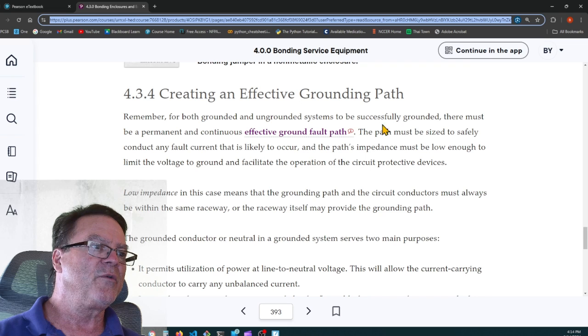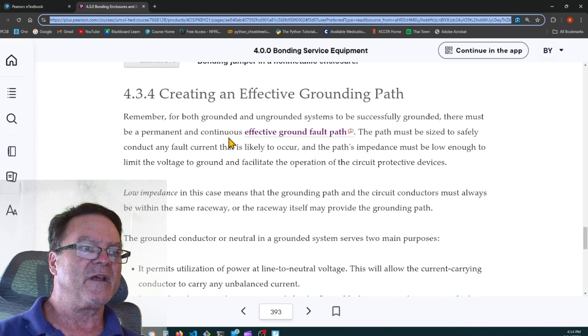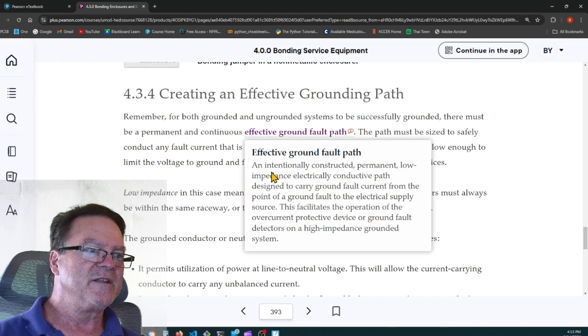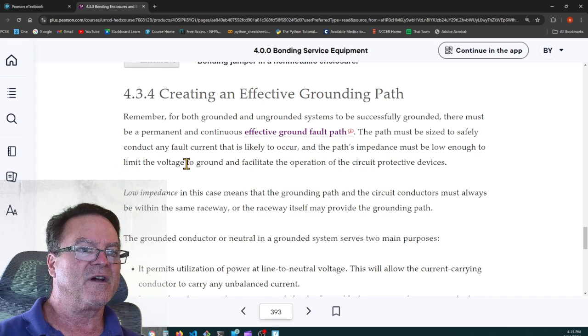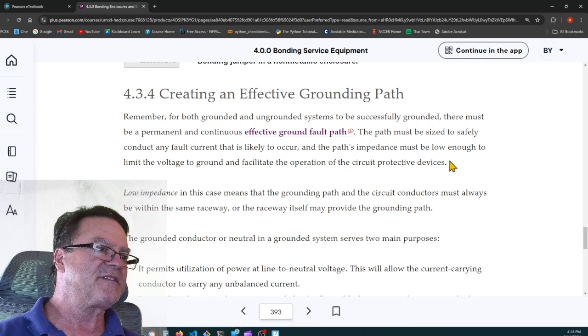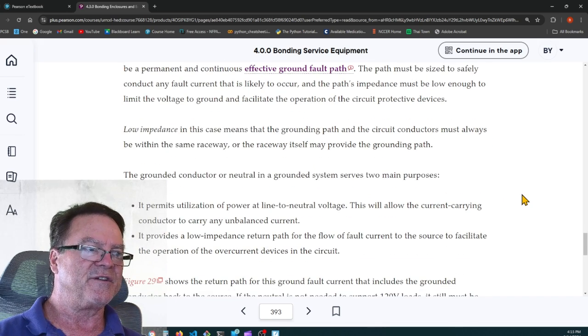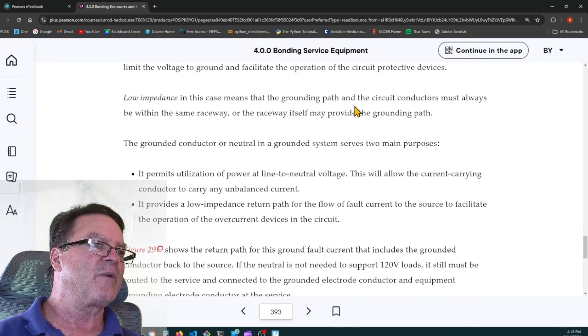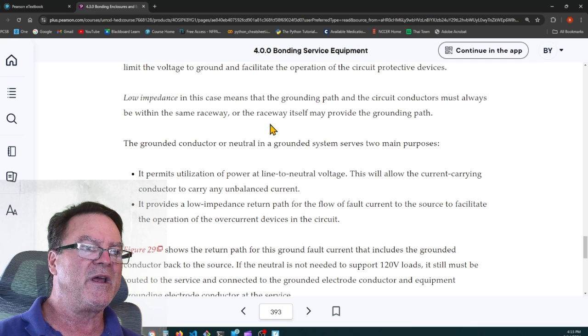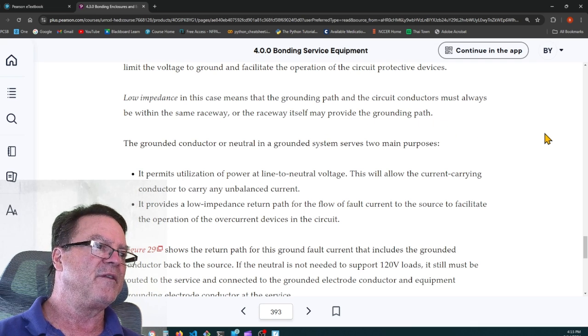Remember, for both grounded and ungrounded systems to be successfully grounded, there must be a permanent and continuous effective ground fault path. It's an intentionally constructed permanent low impedance electrical conductive path designed to carry ground fault current from the point of ground fault to the electrical supply source. This facilitates the operation of the overcurrent protection device or ground fault detectors on a high impedance grounded system. The path must be sized to safely conduct any fault current that's likely to occur, and the path's impedance must be low enough to limit the voltage to ground and to facilitate the operation of the circuit overcurrent protection device. Low impedance in this case means that the grounding path and the circuit conductors must always be within the same raceway, or the raceway itself may provide the grounding path.